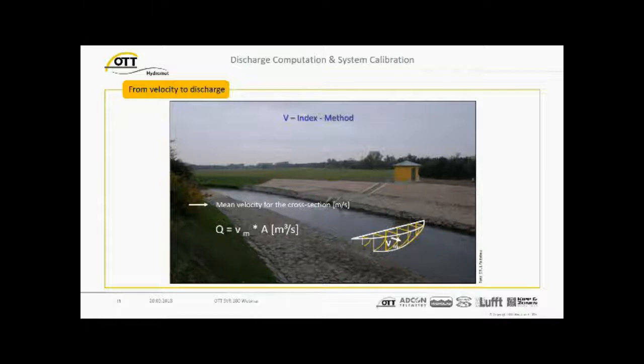Again, for discharge, Q, you will need the mean velocity in your cross-section, and you will need the cross-sectional area itself. We don't measure the mean velocity directly. What we do is we measure the surface velocity, which is bigger than the mean velocity, of course. The surface velocity is measured by the SVR 100. So that means we need to correct the surface velocity. We need to multiply it with a correction factor, a calibration factor.